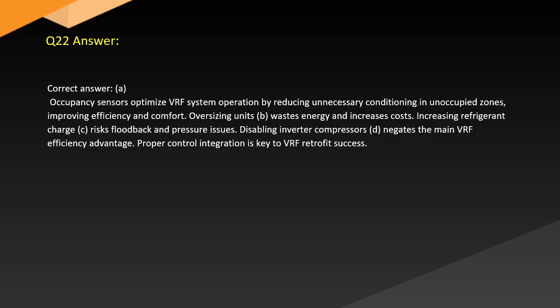Answer. Correct answer. A. Occupancy sensors optimize VRF system operation by reducing unnecessary conditioning in unoccupied zones, improving efficiency and comfort. Oversizing units, B, wastes energy and increases costs. Increasing refrigerant charge, C, risks floodback and pressure issues. Disabling inverter compressors, D, negates the VRF efficiency advantage. Proper control integration is key to VRF retrofit success.